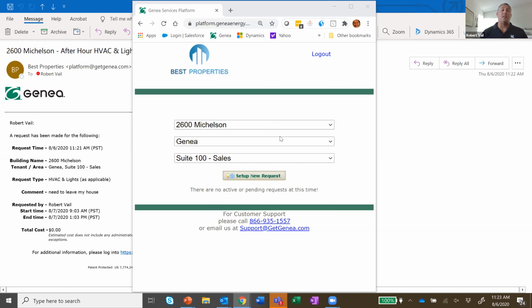We teach the tenants, if you're coming in on Sunday and it's 100 degrees out, put your request in 2 hours early. During business hours, especially in extremely hot areas like Texas, you probably wouldn't shut the building totally off and go fully on demand Monday through Friday. You'd run a minimum load, enough to support the central plants or chillers, running the main lobby and maybe a couple vacant floors, so when somebody needs to come in, it ramps up service. So it depends mechanically on how the building works.